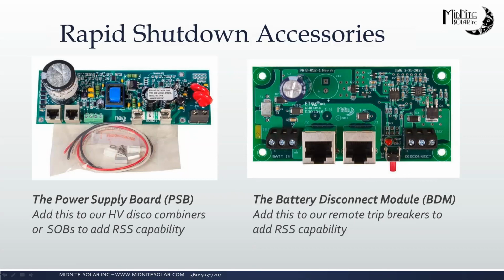And here's your power supply board and your battery disconnect module we talked about. You'll notice both have 2 jacks, so you daisy chain all this stuff together. The power supply board for the combiners does have an upstream and downstream jack, and polarity on that is important because remember, this is charging the batteries downstream, so there are diodes blocking one from feeding another one upstream. So just make sure you pay attention to that. There is no concern over these two.